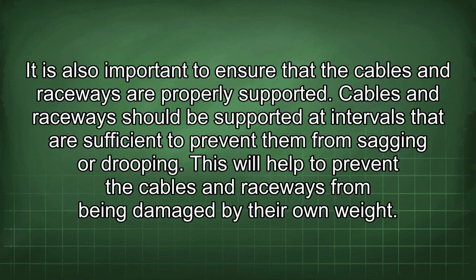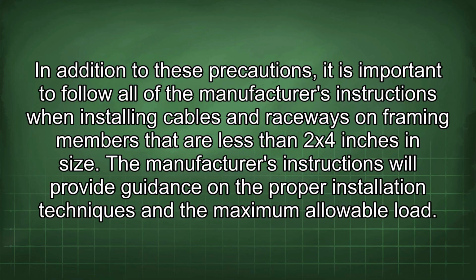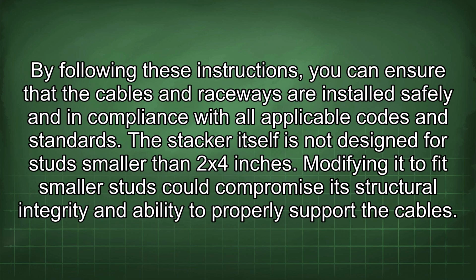It is also important to ensure that the cables and raceways are properly supported. Cables and raceways should be supported at intervals that are sufficient to prevent them from sagging or drooping. This will help to prevent the cables and raceways from being damaged by their own weight. In addition to these precautions, it is important to follow all of the manufacturer's instructions when installing cables and raceways on framing members that are less than 2x4 inches in size. The manufacturer's instructions will provide guidance on the proper installation techniques and the maximum allowable load.